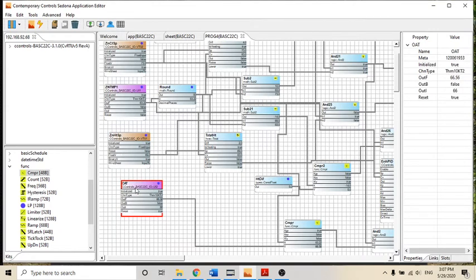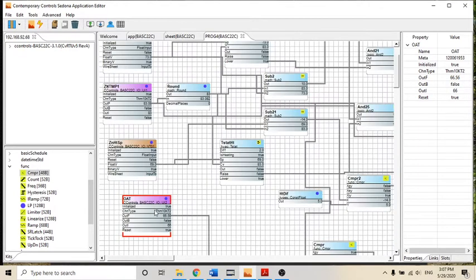So it's this one right here. It's the outside air temperature. It's again just a type 2 10K thermistor that is stuck right now in a cup of water. So it's reading 66.56 degrees and it stays kind of steady because the water is warming up on the slower side. Zone temperature is 82.5 or 82.47 degrees. Everything else stayed the same.